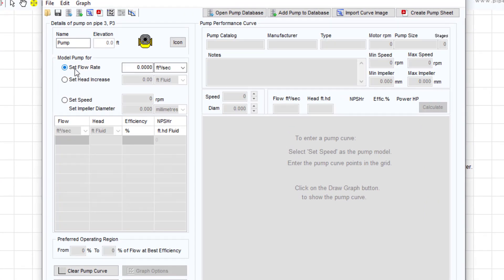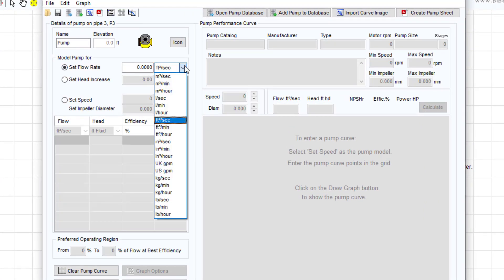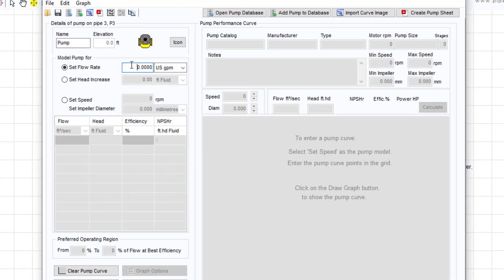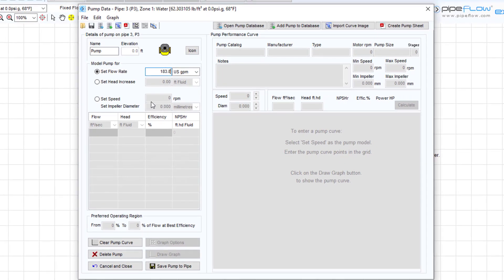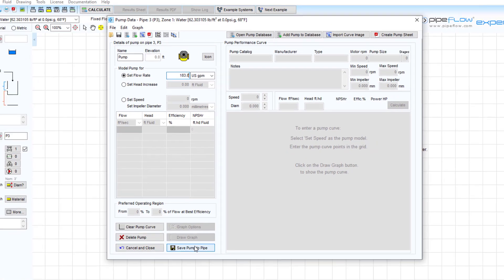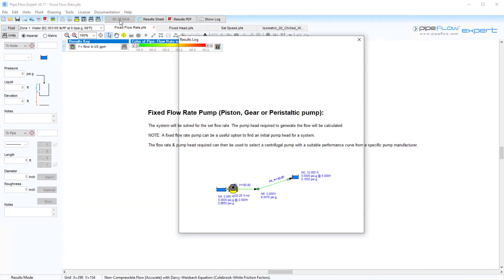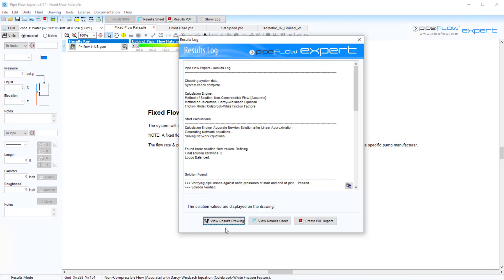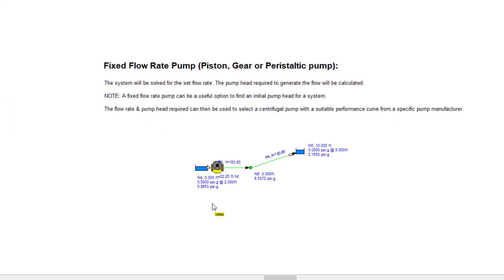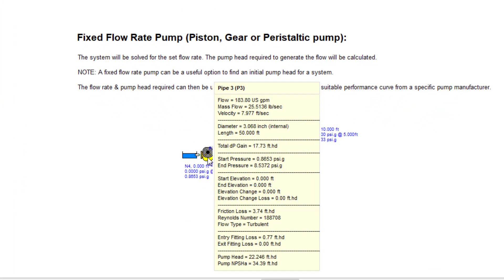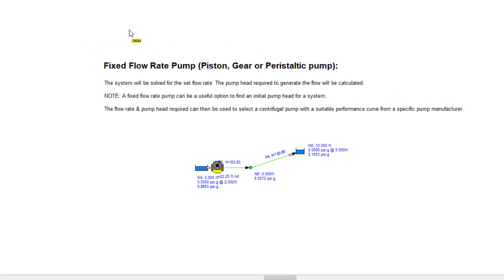First looking at the fixed flow pump. This pump type is used to specify the pump flow rate for a positive displacement pump. The system will be solved and the required head from the pump will be calculated. In this example we see that the pump would need to add about 22.25 feet of head to produce the 183.8 US gallons per minute flow rate we set.